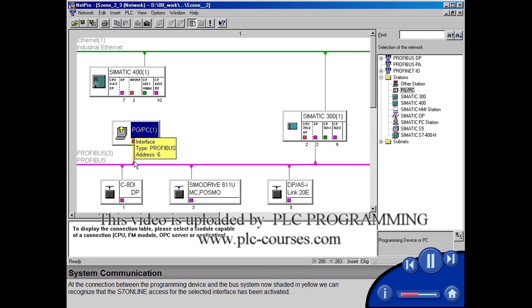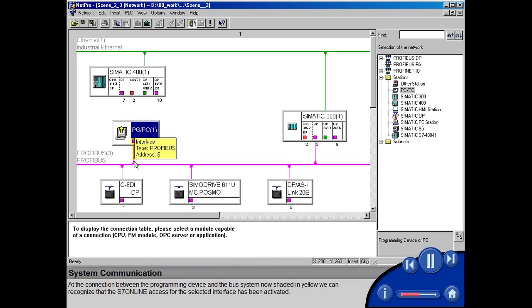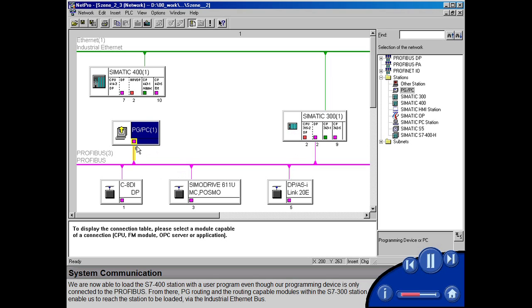At the connection between the programming device and the bus system, now shaded in yellow, we can recognize that the S7 online access for the selected interface has been activated. We are now able to load the S7400 station with a user program, even though our programming device is only connected to the PROFIBUS.